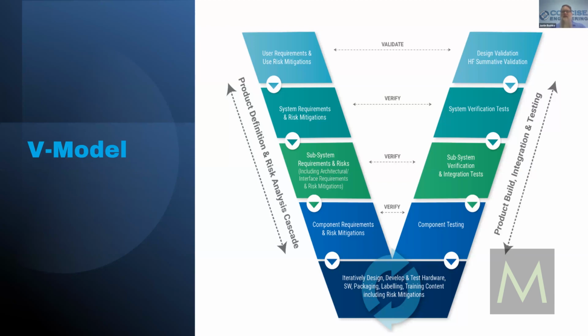When you're getting into this, here is another model that a lot of people use. This is the V model. This can be used in pretty much any way you want to view it. It could be just general requirements. It could be system level and all the distilled requirements. It could be just software requirements or anything along those lines. You could even build one of these for usability itself if you wanted to. But basically, it starts at the top left. You have your top level requirements for the user. Then you have your sub-level requirements, which are basically your design inputs and the sub-levels of those design inputs. And all of those lower ones are passing across to unit level testing, component testing, sub-assembly testing, system level testing, which is all verification.